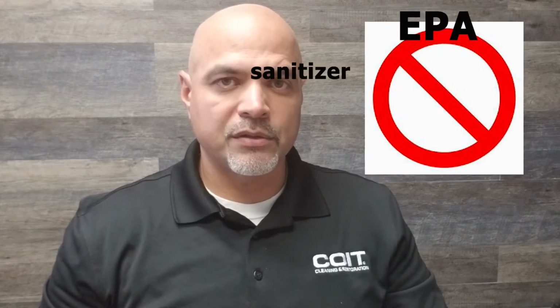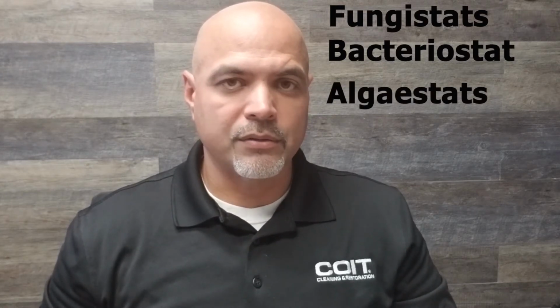A variety of cleaning products may be used within an HVAC cleaning process. The three that we're going to be discussing today are an antimicrobial, a disinfectant, and a sanitizer. An antimicrobial is any substance or mixture of substances designed to kill, prevent, destroy, or mitigate any microorganisms. The term sanitizer is often misused or misunderstood within our industry. A sanitizer is a substance or a mixture of substances designed to kill bacteria, but not necessarily all bacteria on a surface. At this time, the EPA has not approved any sanitizers, disinfectants, or fungicidal products within a duct system. They have approved products such as fungistats, which inhibit the growth of fungi, bacteriostats, which inhibit the growth of bacteria, algistats, which inhibit the growth of algae, and deodorizers.